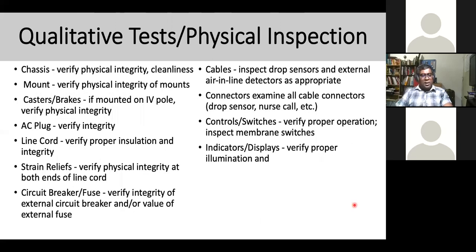So when you talk about other parts of physical inspection, you're going to check the chassis, the mounting of the physical part of it, caster brakes, AC plugs. Sometimes you get an infusion pump with a holder that can move around. So they've got small wheels, casters and the brake, and the IV pole. Make sure that all are in good condition. AC plug, line cord, strain relief, both ends. Then circuit breaker and fuse, if you have anything linked together, but normally these are part of the plug line. Check the fuse using the right value.